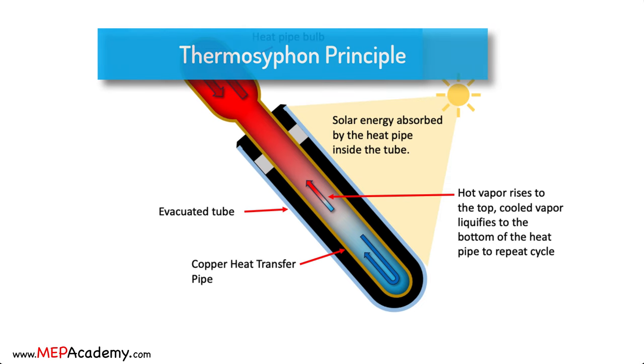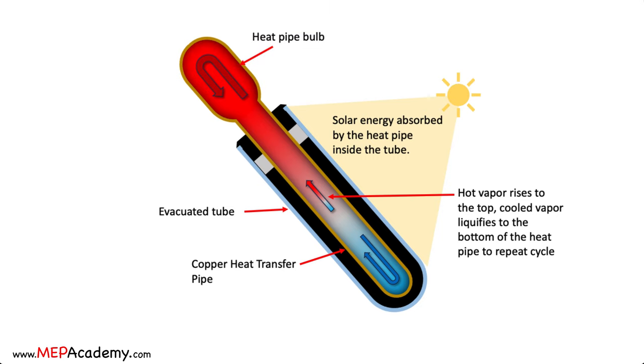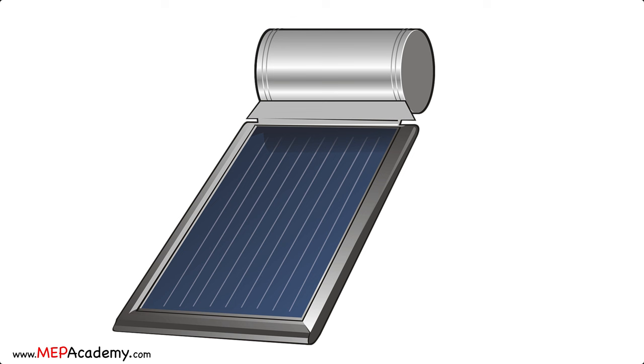The core principle behind passive solar water heaters is thermosiphon. As water absorbs heat, it becomes lighter and rises. Simultaneously, colder, denser water descends to replace it, creating a natural circulation of water through the system. The heated water typically rises from the collector to a storage tank located at a higher elevation. This tank is positioned above the collector to facilitate the thermosiphon effect. The warm water is stored in this tank until it is needed. When hot water is required, it is drawn from the storage tank. The cold water that enters the collector to replace it completes the natural circulation loop.